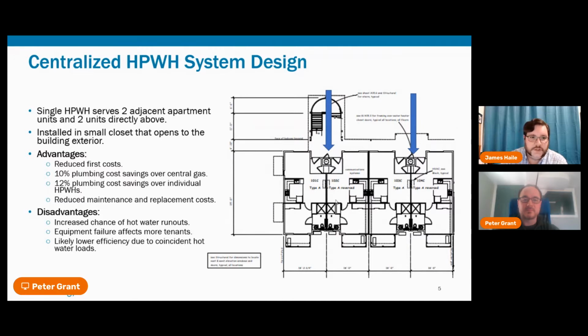And well, the disadvantages of this configuration are all things that you would expect, such as increased hot water runouts due to higher loads per water heater. The configuration had a big advantage in reduced first costs relative to other options, including central gas. This is, of course, important for affordable multifamily housing, but it's very important for multifamily in general and for heat pump technology adoption, as first costs are often the only things that builders are concerned about.